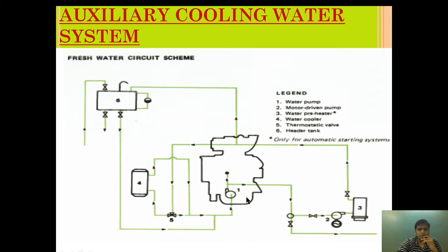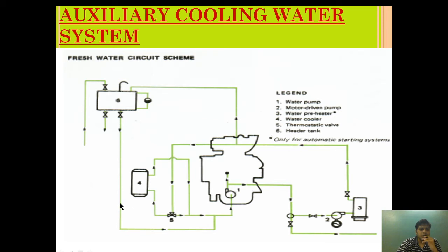In summary: water coming out from the engine is heated and routed to the mixing point. The amount of water mixing is controlled by a thermostatic valve so that cooled and heated water are blended to the correct temperature before being fed to the system. To compensate for any leakage in the system — whether through pump glands or the cooler — a header tank is provided to make up the loss.